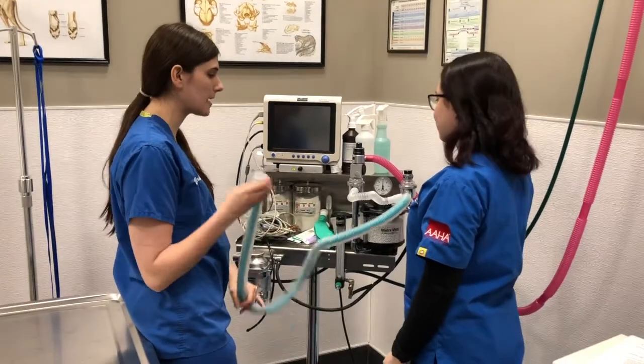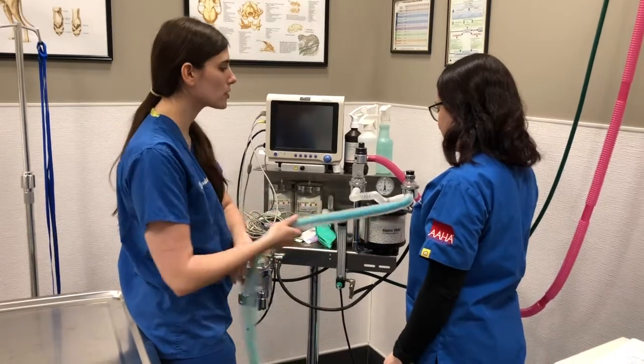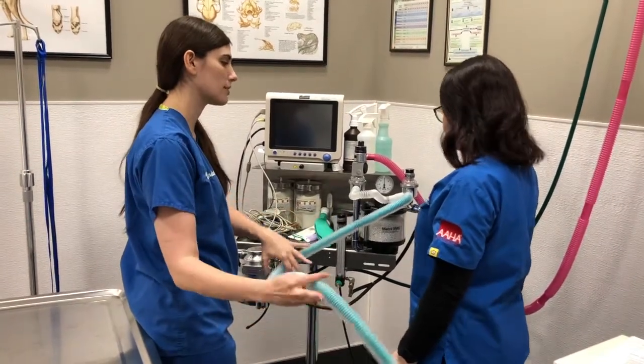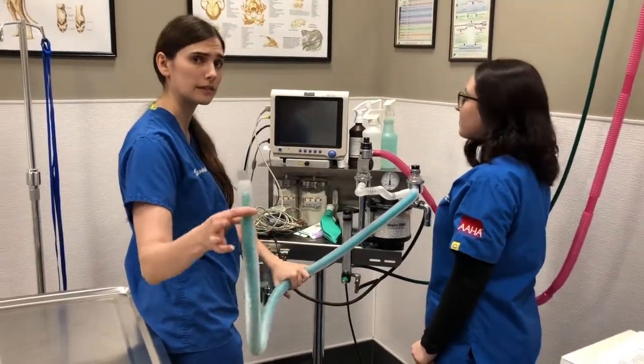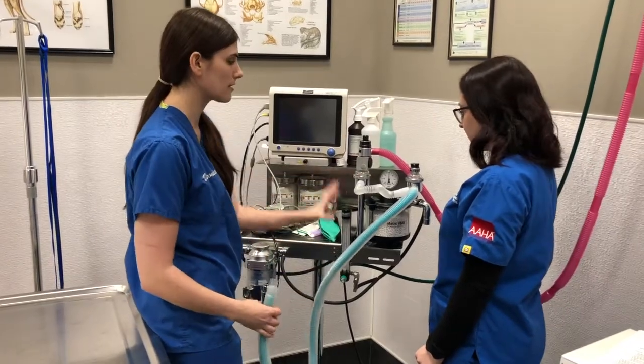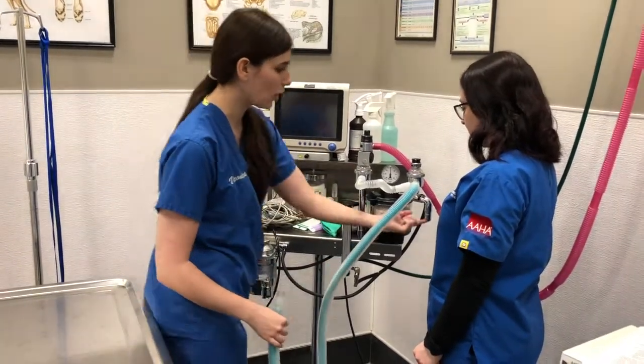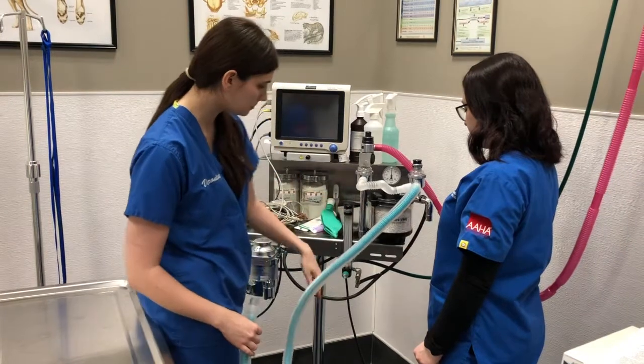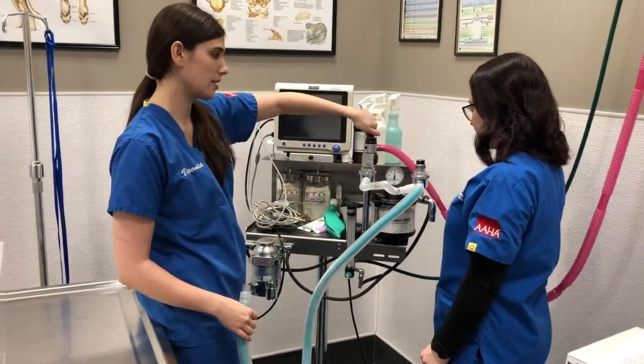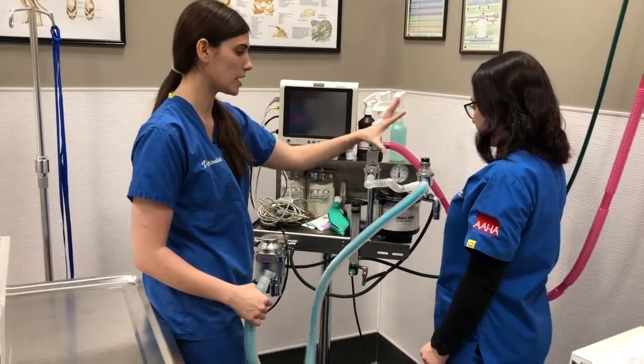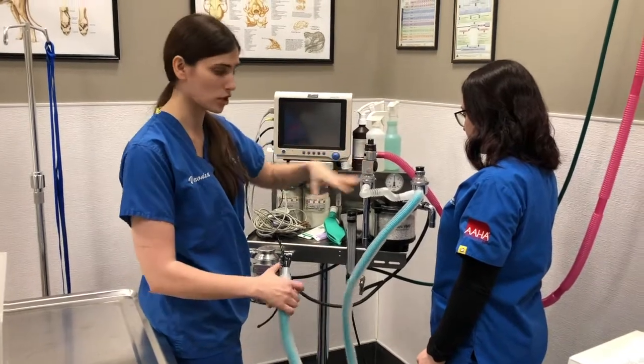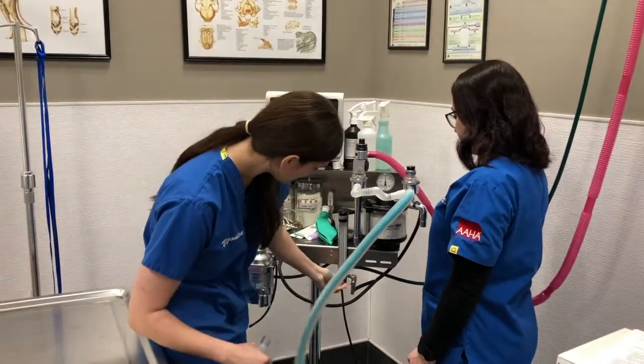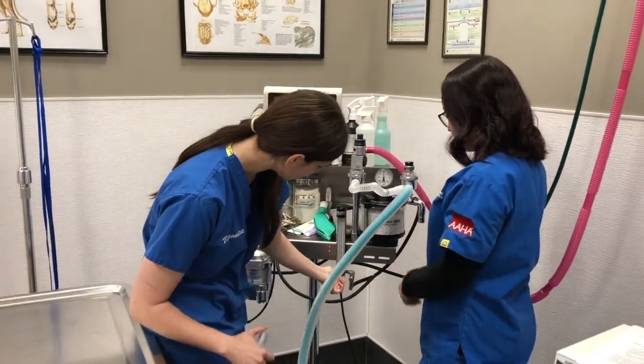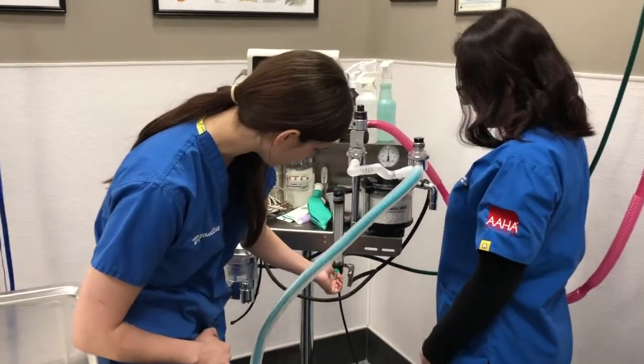So we're going to do a leak test on our anesthesia machine. There are two different ways of doing this, or two different steps that you need to do when you're testing leaks. The first thing that we're going to do is test the entire machine itself. So we've taken off the rebreather bag that would normally go here. I've closed this valve so that all of the oxygen stays in this machine. What I'm going to do is put the oxygen to 1 liter.